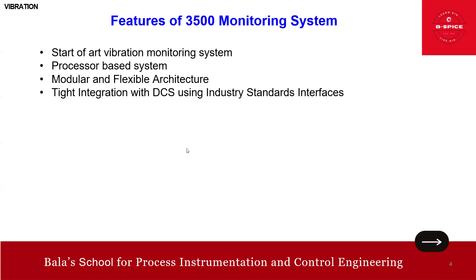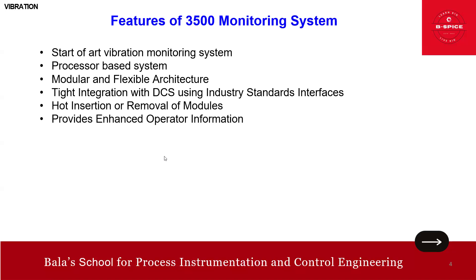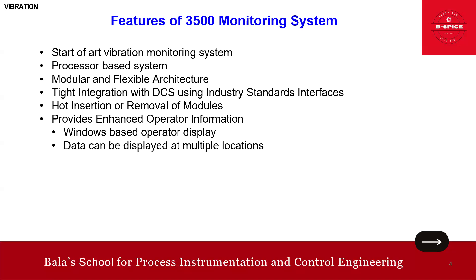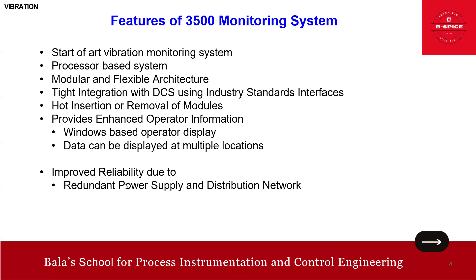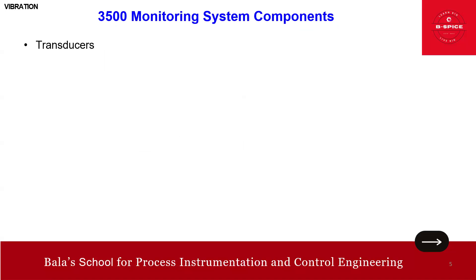Key features of the 3500 include good integration with DCS using industry-standard interfaces, hot insertion and removal of modules, enhanced operator information via a Windows-based operator display, data displayed at multiple locations, redundant power supply distribution network, and triple modular redundant relay modules.